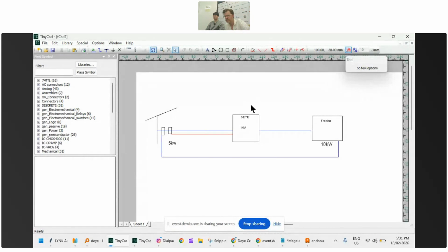The other thing you can do is use the input pins on the Fronius inverter, and you have a relay attached to the generator input in an off-grid system. So as soon as there's AC on the generator input, before the inverter is even synchronized with it, that relay is going to close, and you key that to the inputs on the Fronius, but that will only ramp them down to like 100 watts. It won't ramp them down to 0, in my experience. So yeah, you don't necessarily need to avoid it. You just need to have it as part of your design process.